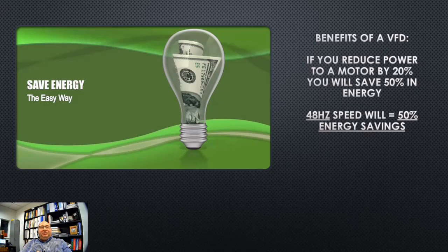So that's pretty neat. This is why we don't really have to run VFD motors at 60 hertz. Sometimes we don't run them at 100%. We run them much lower so we can reap the benefits. If we could get away with 50 hertz or even 48 hertz as a maximum speed, then we will yield 50% of energy savings. That's pretty awesome.